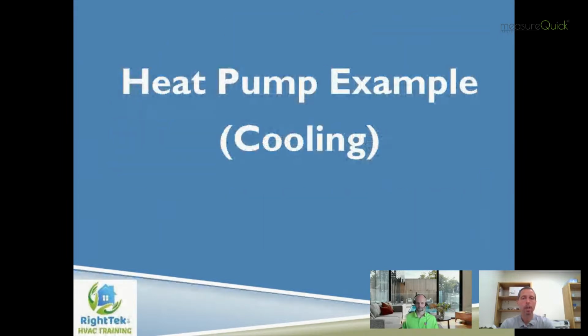So when we look at sizing a heat pump for cooling only, which in the current Manual S was the only way you did it, you sized it for cooling and hoped for the best on the heating side, which sometimes meant some really large heat strip kits that frankly are not the most energy efficient way we could be doing things. When people put in heat pumps, not only do they want to be comfortable, but they're thinking it's going to be a fairly energy efficient way of heating and cooling their home.